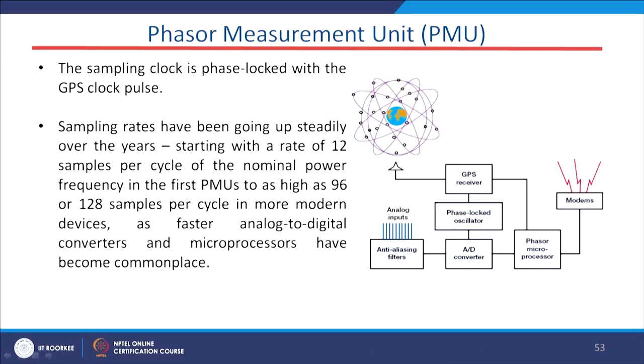The PMU sampling clock is phase-locked with the GPS clock pulse — this is very important. The phase-locked oscillator and the GPS clock are locked together, so that the ADC will start converting and sampling the analog signal to the digital domain.